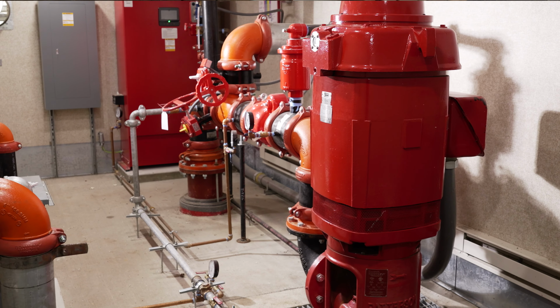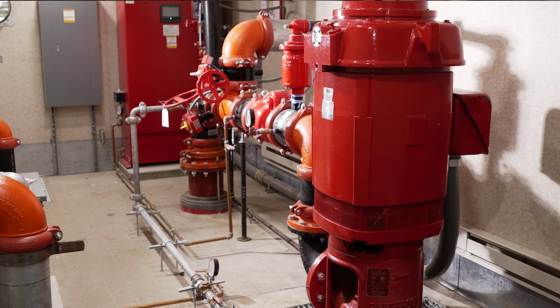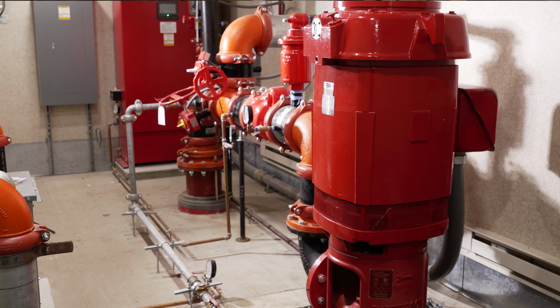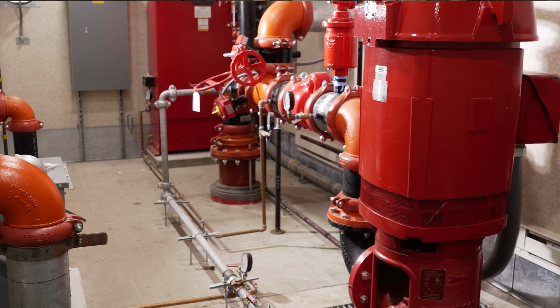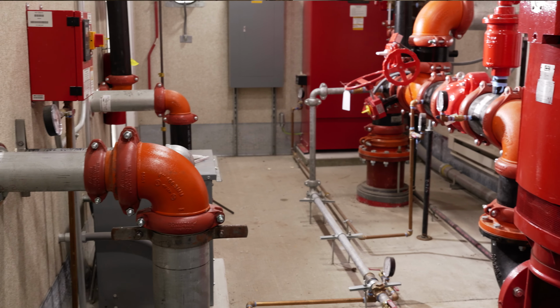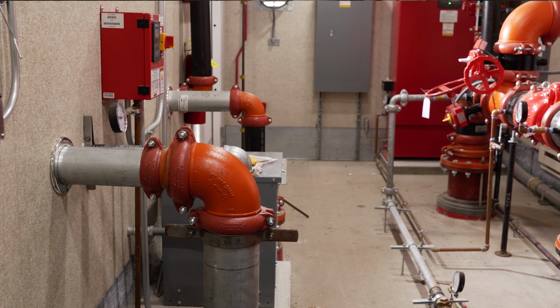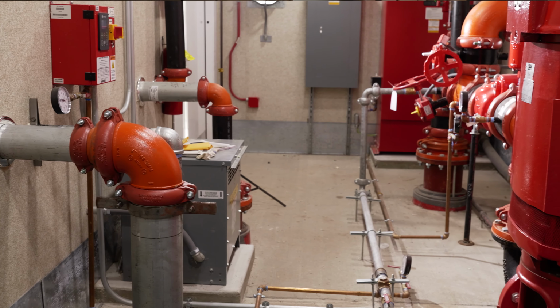The jockey pump and the fire pump are all configured for automatic operation. While the fire pump will only operate in the event of testing or a fire, the jockey pump's purpose is to maintain pressure in the mains from the pump to the valve assemblies. This pump should not normally run, but it is in place to maintain system pressure in the event of any leakage in the underground pipe, if a check valve should develop a leak, or to bring the system up to pressure following any system maintenance that requires shutdown of a system. Should the jockey pump be found to run frequently, the source of the water loss should be investigated.